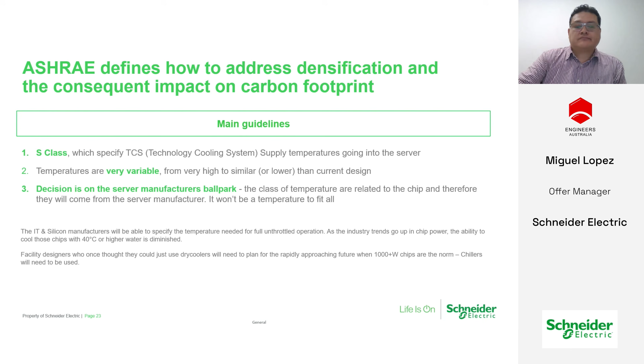So ASHRAE at the moment has created so-called S-class classifications for the TCS fluid, ranging from S30 to S50. So you've got S30, S35, S40, S45, and S50. The number essentially refers to the supply water temperature, from 30 to 50, and the facility water loop's corresponding water temperatures. Now, once again, going back to the server manufacturer or the chip manufacturer, Dell, Hewlett-Packard, who are adopting chips from NVIDIA and others, they will be designating whether the water temperature should be closer to 50 degrees or as low as 30 degrees. I say that because should you not follow that guidance, then obviously you're voiding warranties and causing issues with the NVIDIA chip and so forth. And that's something that you don't want the IT managers coming back and challenging your design on.